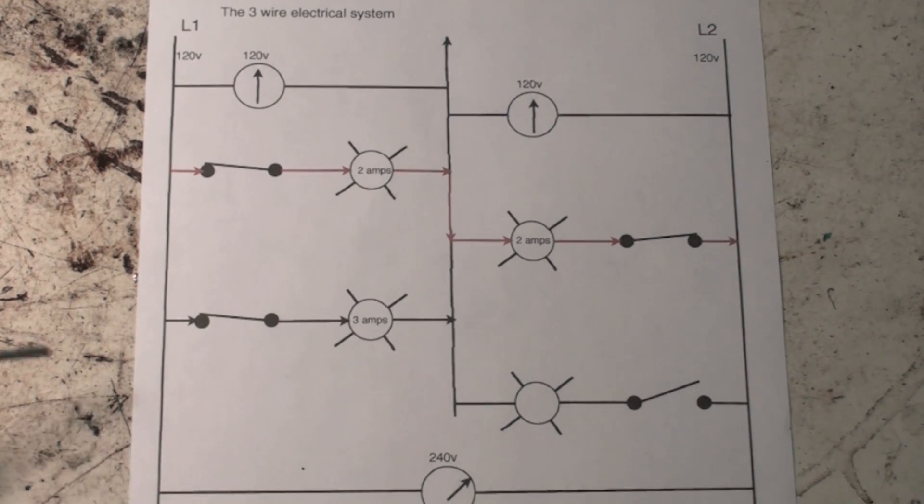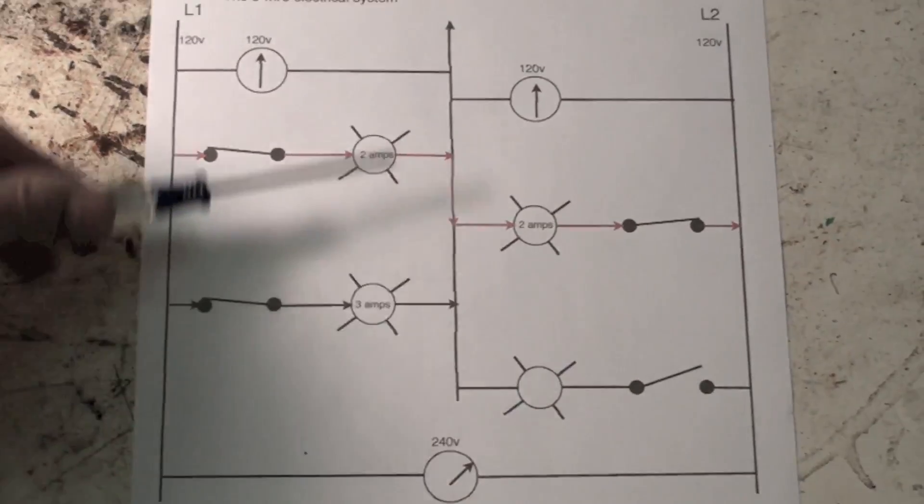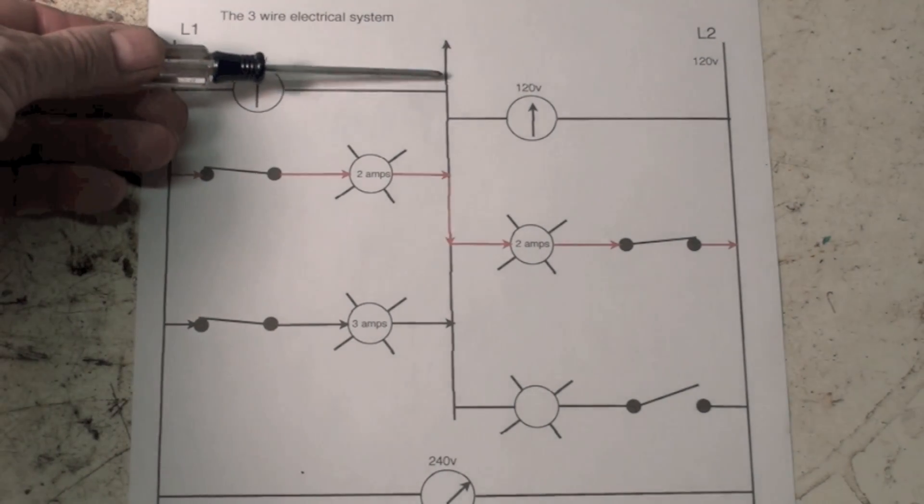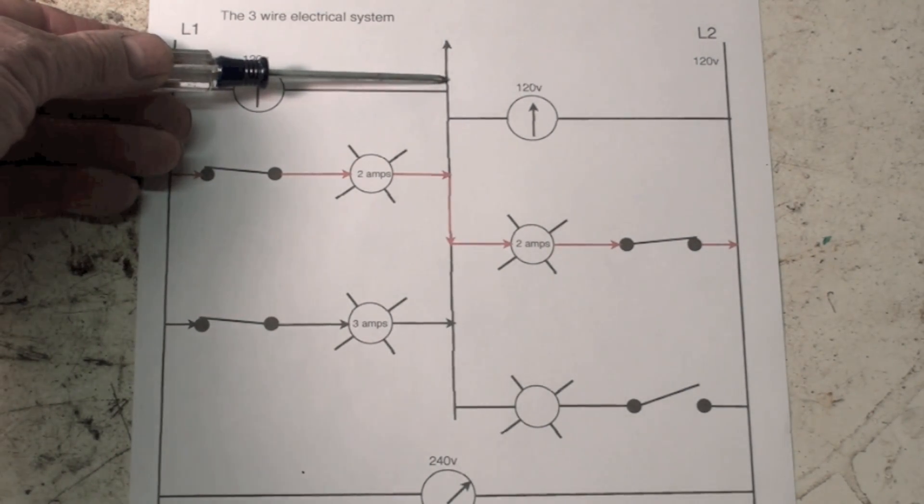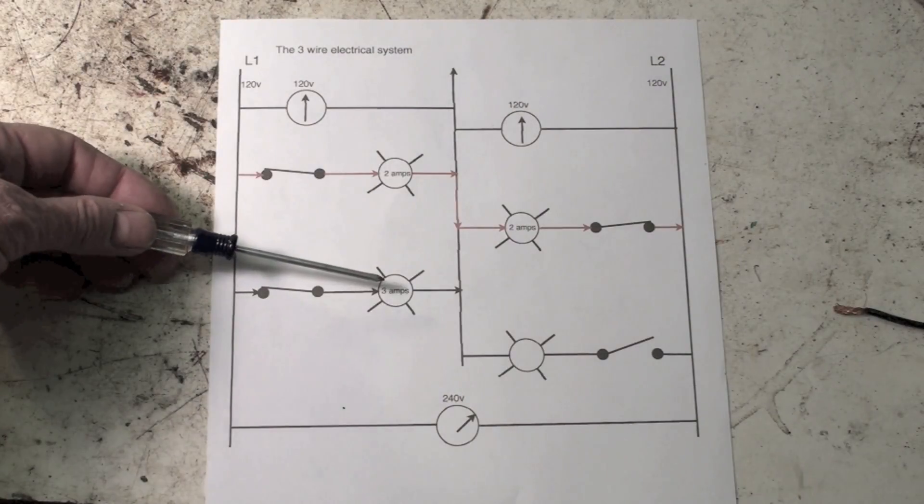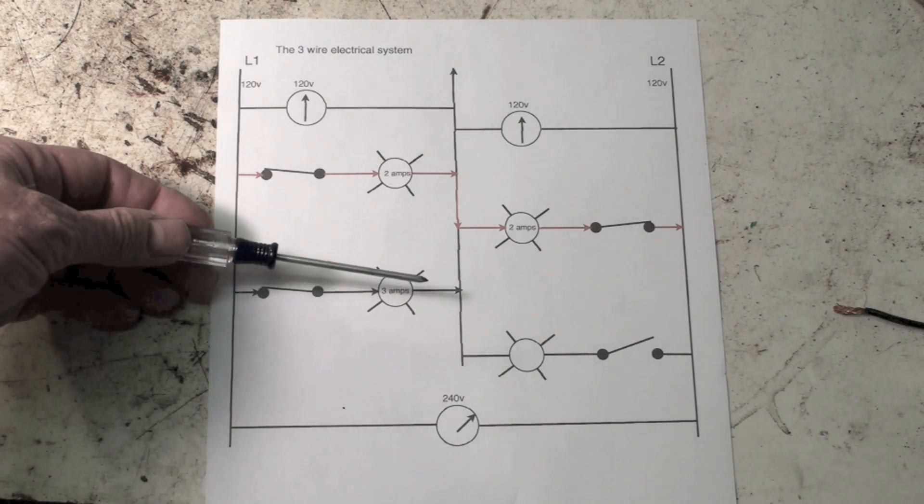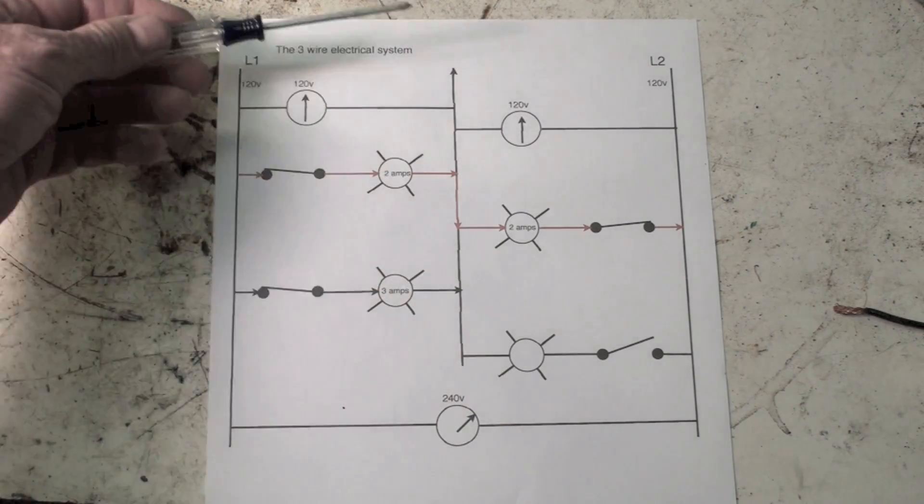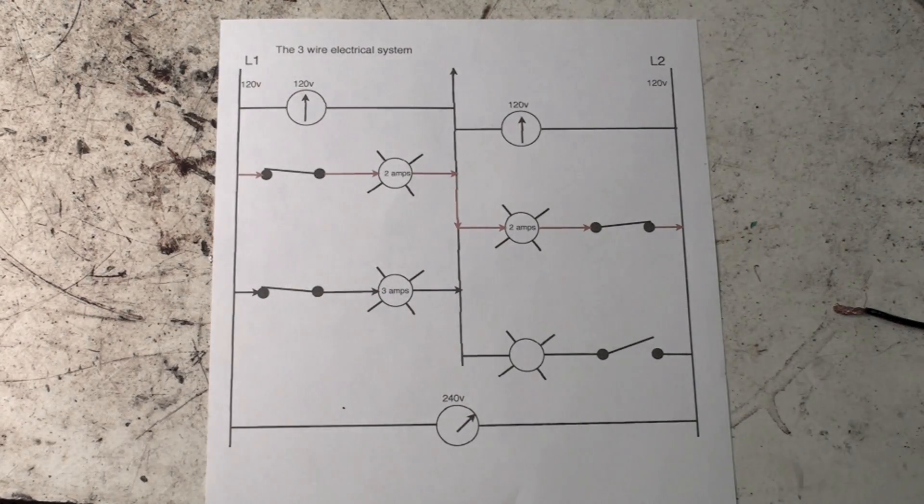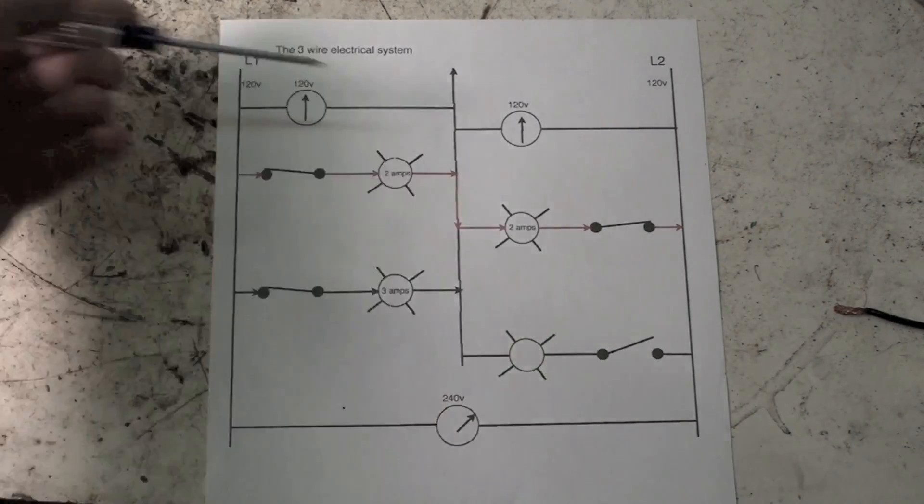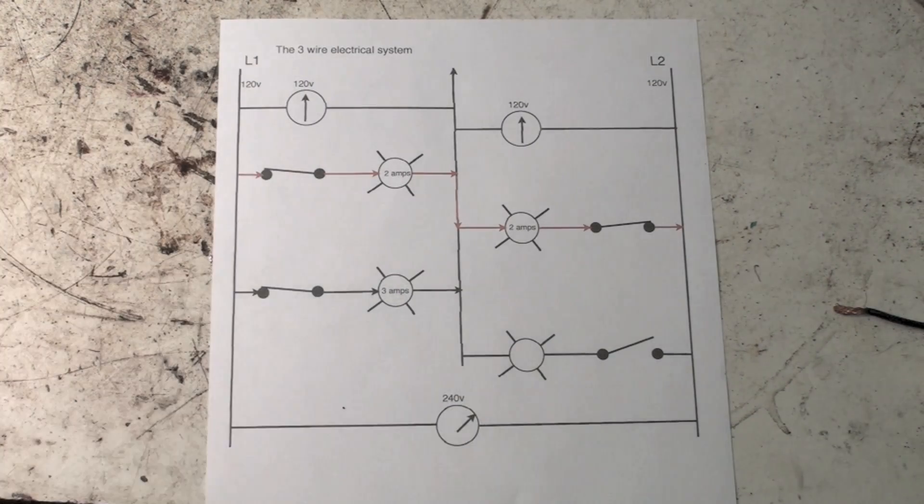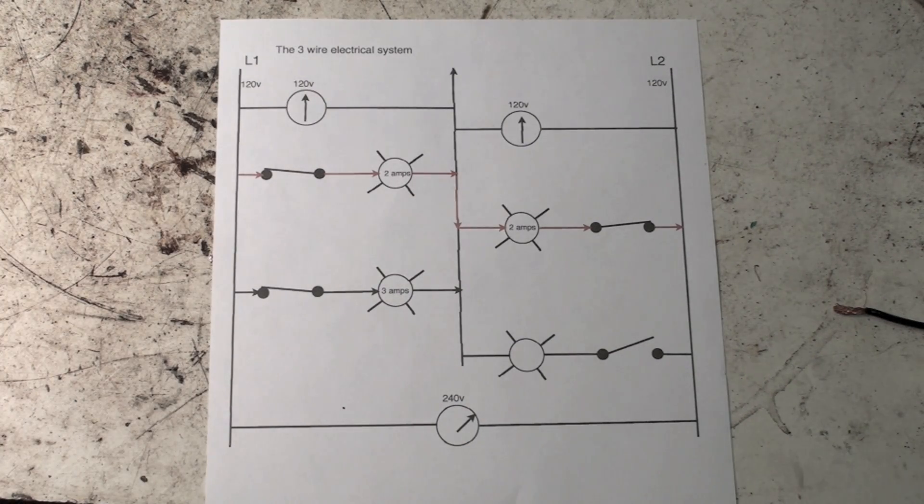What happened to the other 3 amps? It went through the neutral. So it's an unbalanced load. If I clamp the neutral here, I will read 3 amps because that's what the imbalance is—it's not being balanced in the panel, so it's being balanced exterior. This neutral will never carry as much load as L1 and L2 do. It will carry only the load that is not balanced in this system. That's how the three-wire electrical system works.